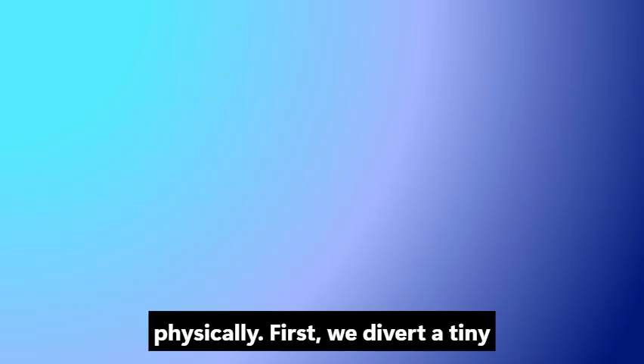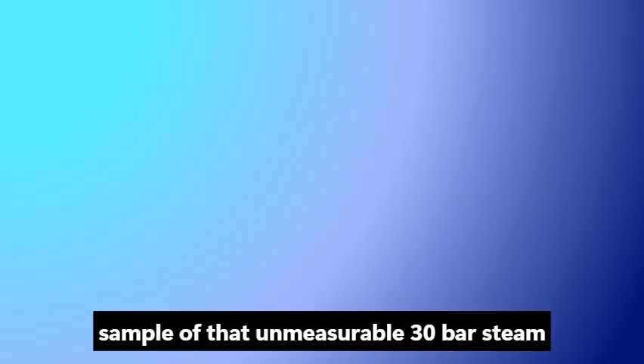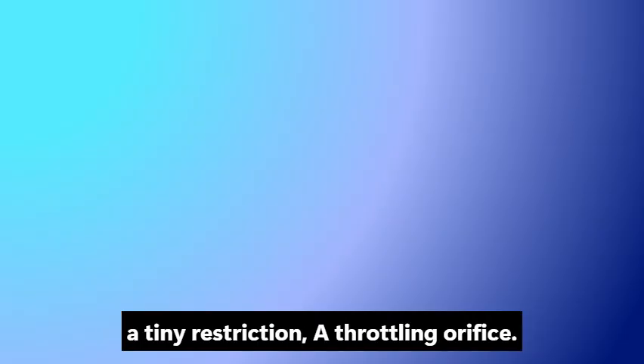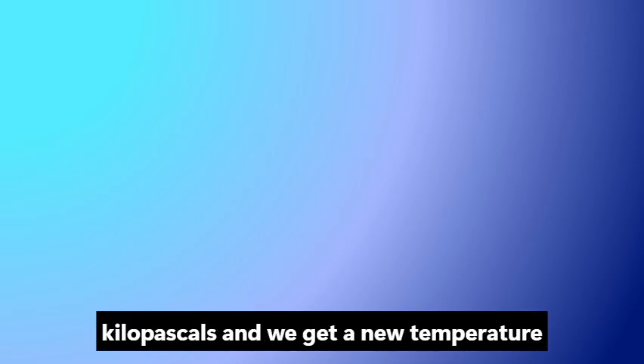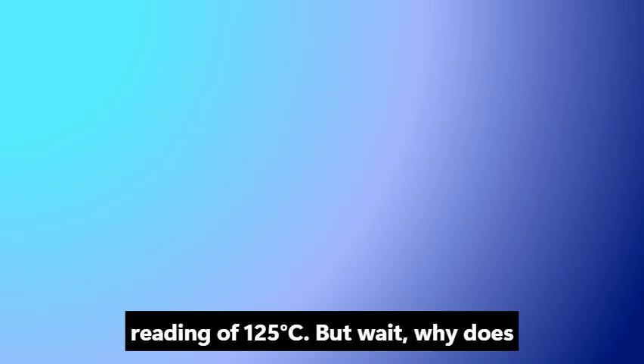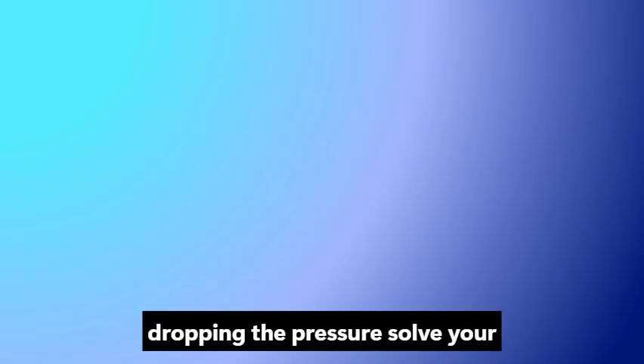Let me explain what it does physically first. We divert a tiny sample of that unmeasurable 30-bar steam from the main pipe and force it through a tiny restriction, a throttling orifice. Okay. We exhaust that throttled steam into a separate chamber where we measure it again. Through that restriction, the pressure violently drops down to 100 kilopascals, and we get a new temperature reading of 125 degrees Celsius. But wait, why does dropping the pressure solve your measurement problem?